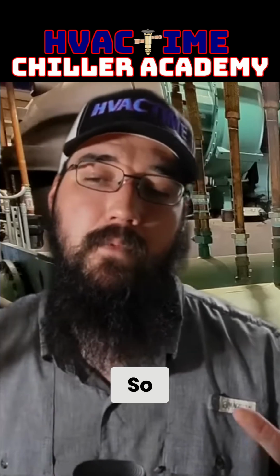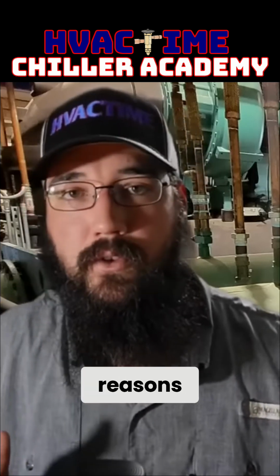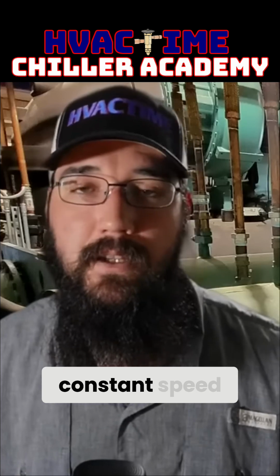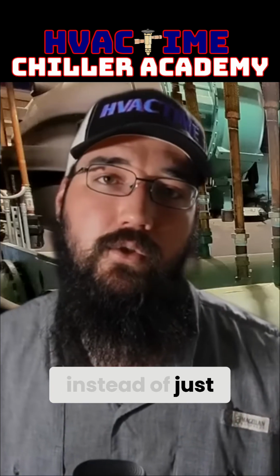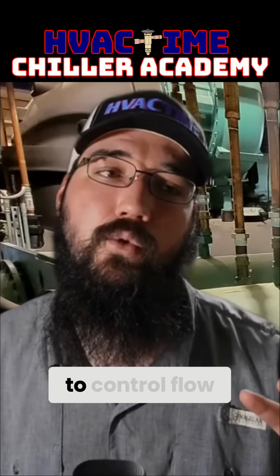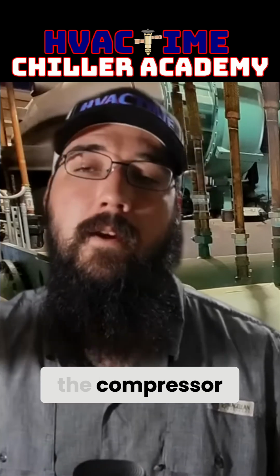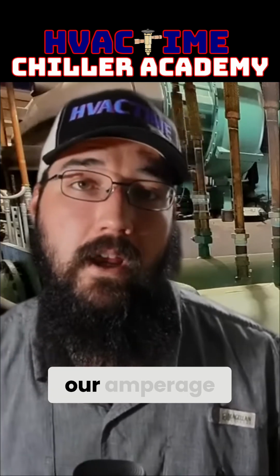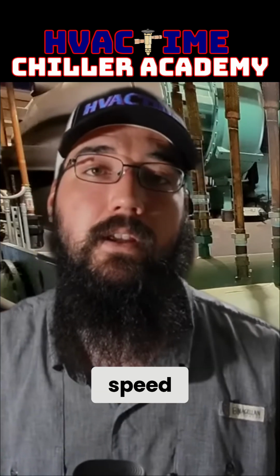Which is one reason we went that direction as an industry. So VSD chillers, one of the reasons they're more efficient than constant speed, is because instead of just using an inlet guide vane to control flow through the compressor, we can actually lower our amperage by lowering the physical speed.